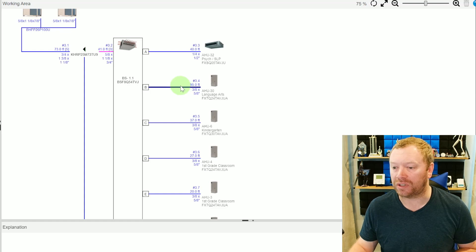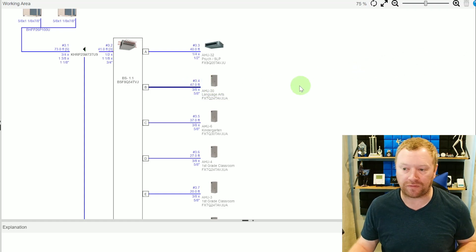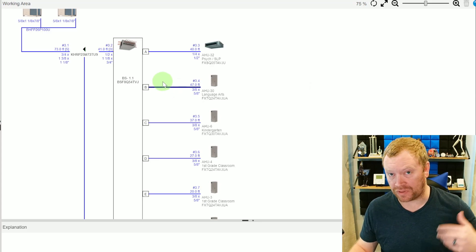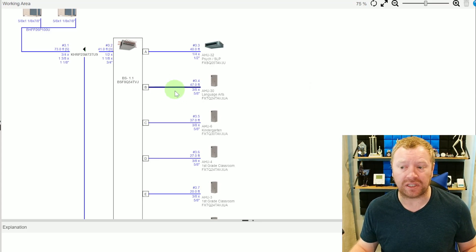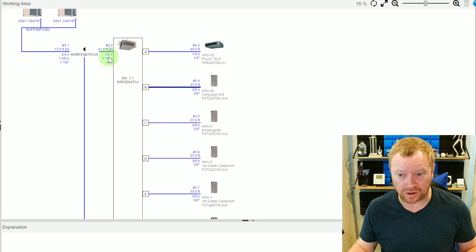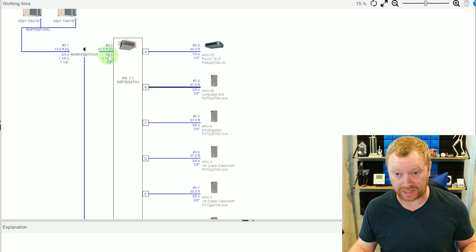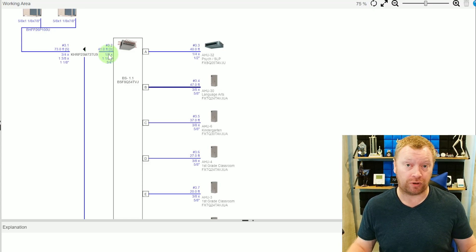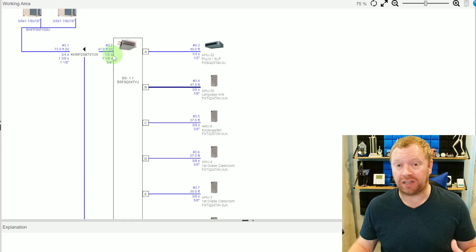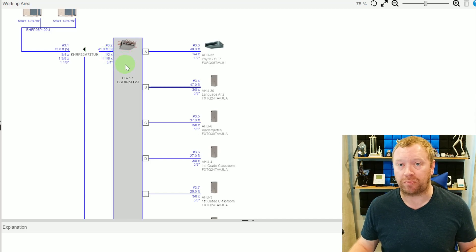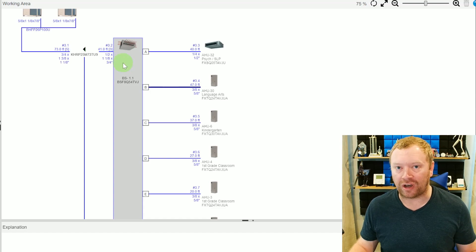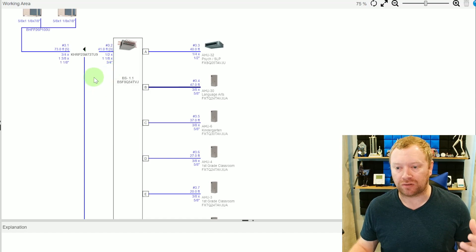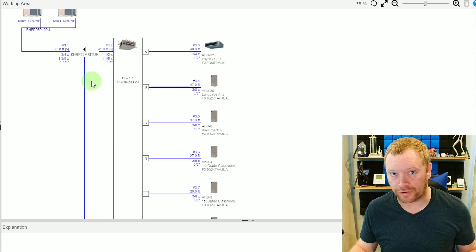I'm going to try to maybe save on labor, save on materials. And so they're like, oh man, this line set here only needs to be, ah, 40, 47 feet. And so when they give us the as builds, they're like, yep, this line set was only 47 feet. Well, now you're going to notice that our line set installed is too big. So the problem goes both ways.